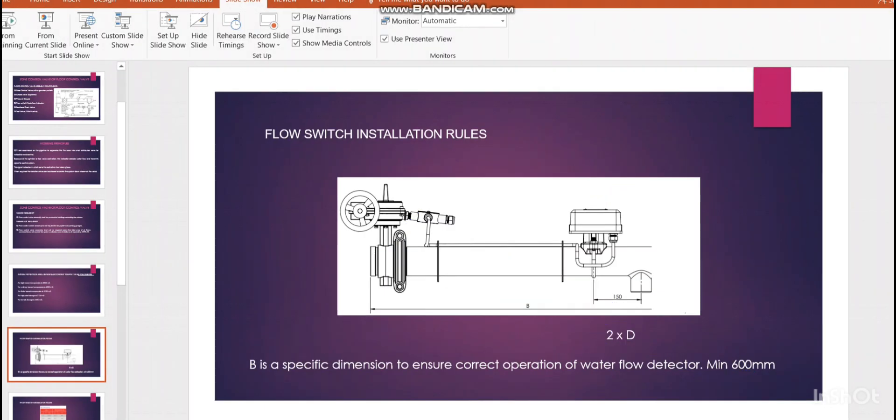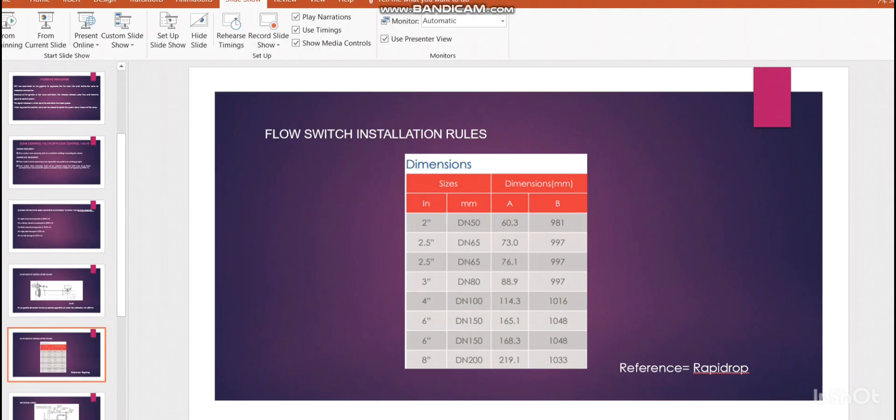Some manufacturers recommend a minimum of 150mm also. The 600mm is common practice, but in addition some manufacturers have specific B values for each pipe size. For example, for one well-known manufacturer, for a 2-inch line the B value is 981mm, for 2.5-inch it is 997mm, and for 8-inch it is 1033mm. In practical cases, we normally keep a minimum of 600mm from the flow switch to the isolation valve.